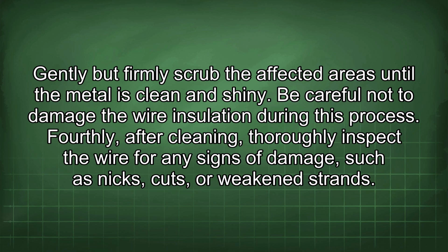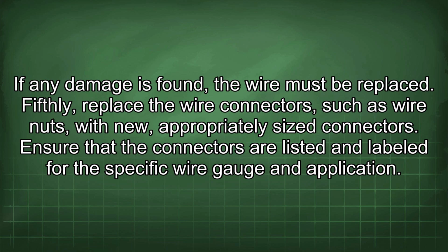Fourthly, after cleaning, thoroughly inspect the wire for any signs of damage, such as nicks, cuts, or weakened strands. If any damage is found, the wire must be replaced. Fifthly, replace the wire connectors, such as wire nuts, with new, appropriately sized connectors. Ensure that the connectors are listed and labeled for the specific wire gauge and application.